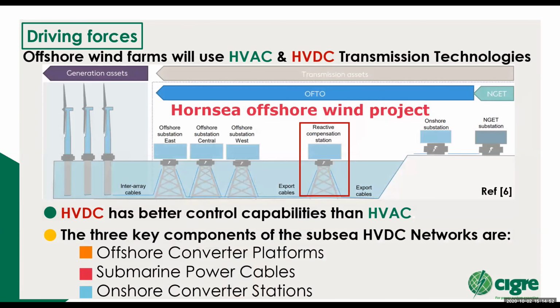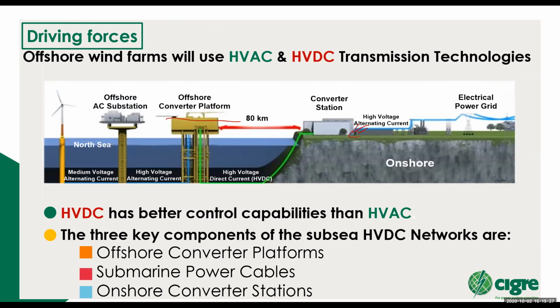For offshore wind systems we can use the conventional HVAC system, but for submarine cables there is the problem of cable capacitive charging effect. So for long distances you may need to use reactive power compensation stations. For example, in the Hornsea HVAC offshore wind system, we use a reactive compensation station to achieve long distance transmission. But HVDC does not have this limitation, and if the distance is beyond 80 kilometers, HVDC will perform better in terms of capital cost and the flexible control of HVDC converters.